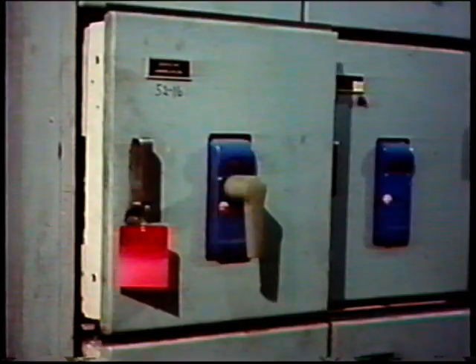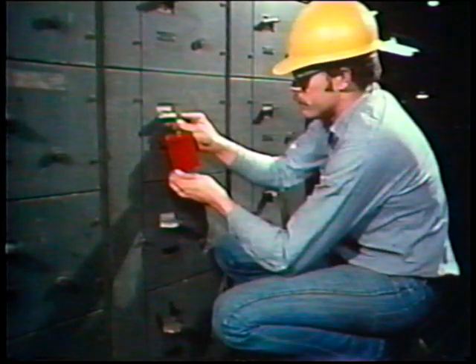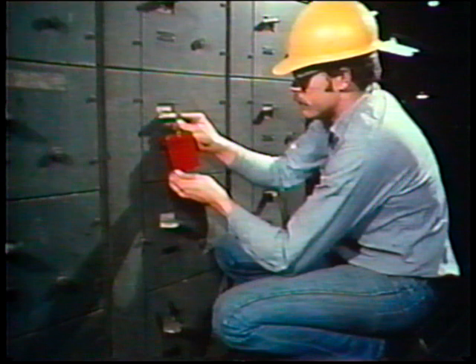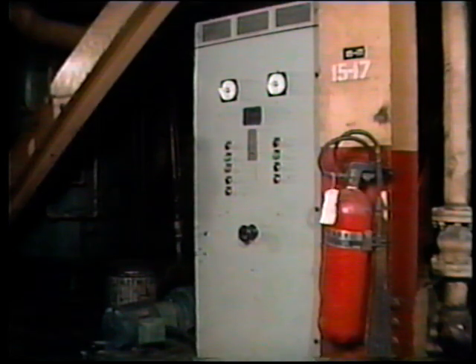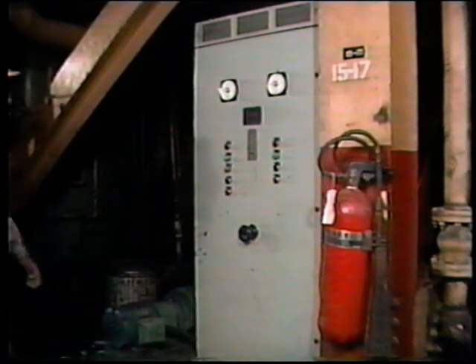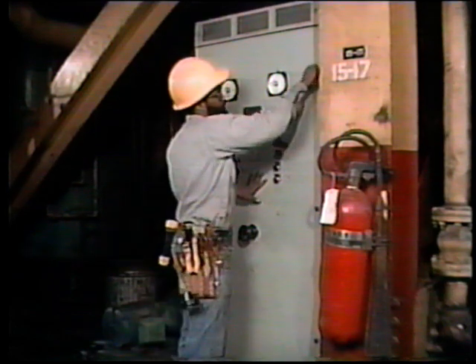Besides taking good care of a synchronous motor, it's important for you to properly maintain its controller. The preventive maintenance procedures for a controller should only be undertaken when a controller is de-energized. So first, have the controller de-energized. Have both the AC and the DC power supplies tagged off. By loosening the knobs at the side of the controller cabinet, the cabinet can be opened.